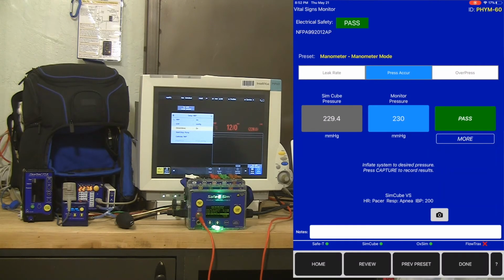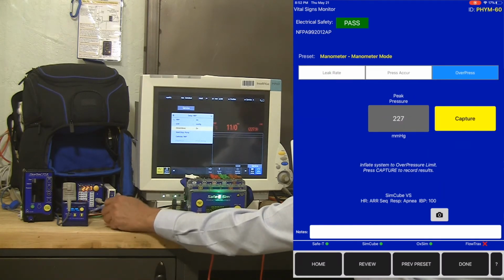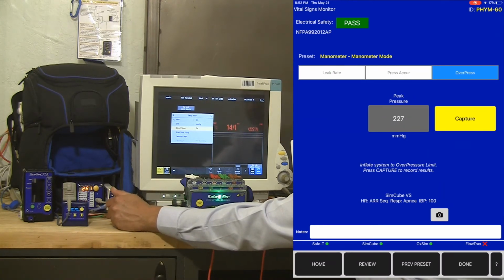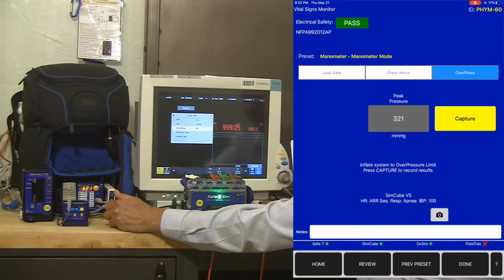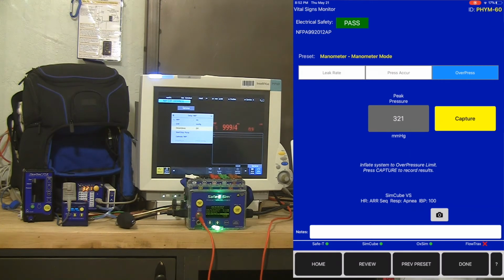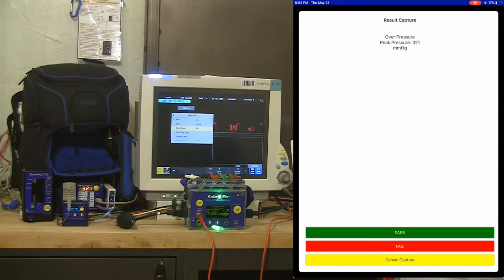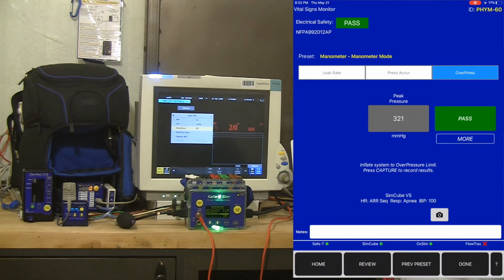Now I'm ready to do an overpressure test, so I'm going to inflate the system higher and look at my peak pressure when the vital signs monitor dumped the pressure for the overpressure limit. We can see the peak pressure was captured by the iOS device because of that real-time data coming from the SimCube via the Bluetooth communications. I hit capture. I've now got my peak pressure at 321 captured. That's a pass, and I am done.